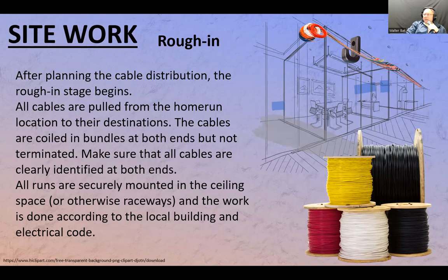Then try to keep them in bundles. Keeping them in bundles gives you an advantage. Let's say there are 15 wires here. You can run each wire independently, so you're going to have to do this wire pull 15 times. Or you can just bundle them. Running 15 wires as data is not that uncommon. You can bundle them in 15 and just do one pull of 15 wires instead of 15 pulls of one wire. Just think about the time that is going to take you one way or the other, right?